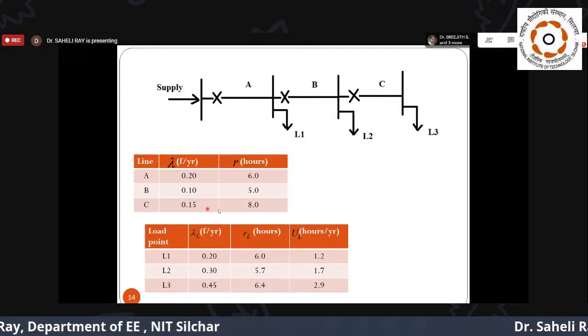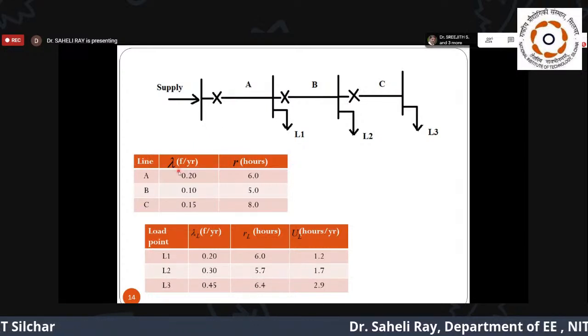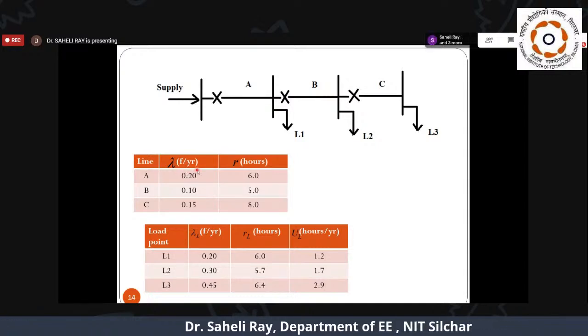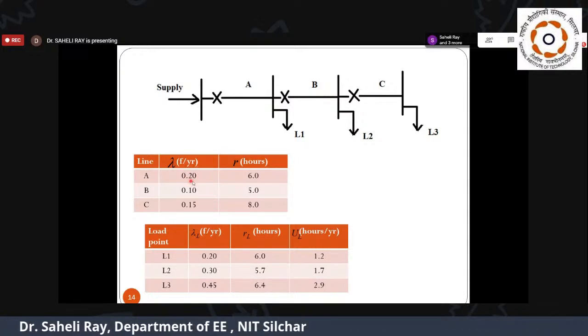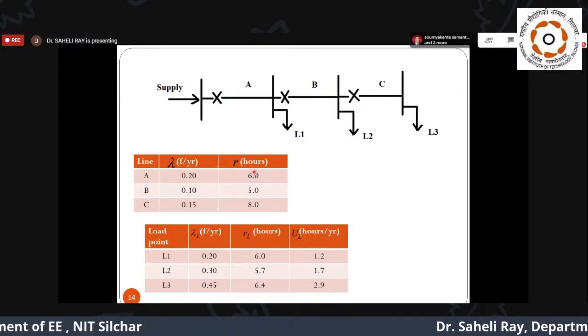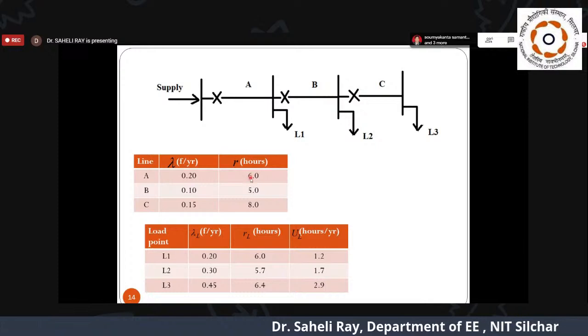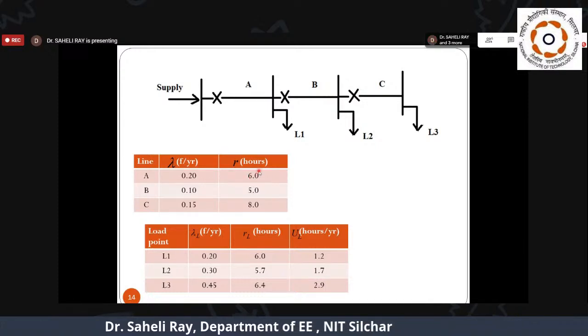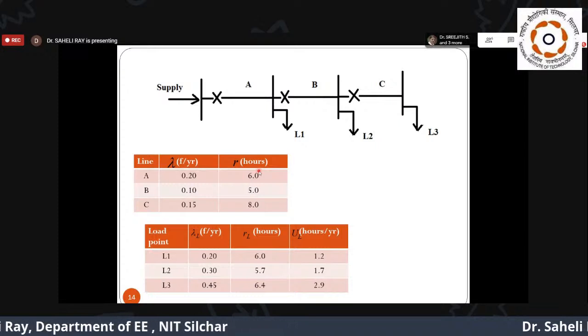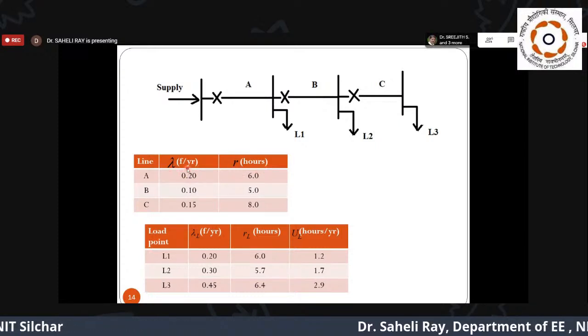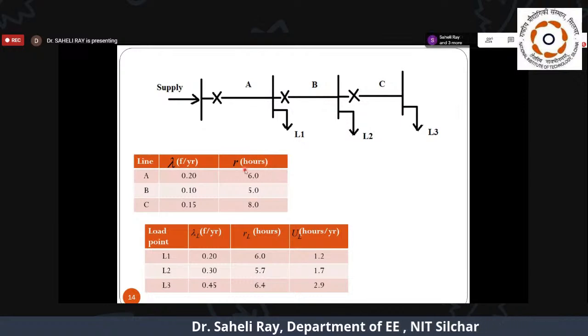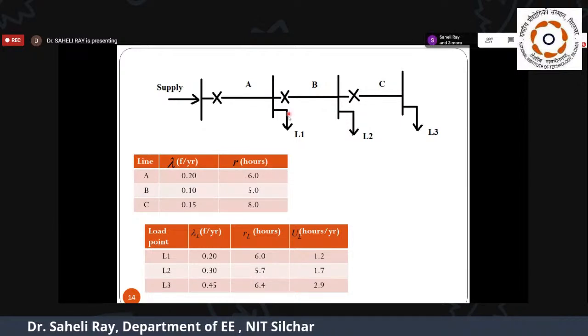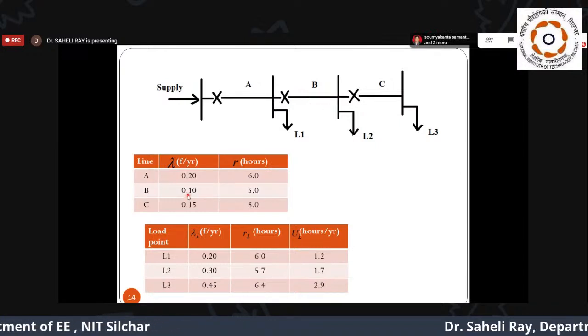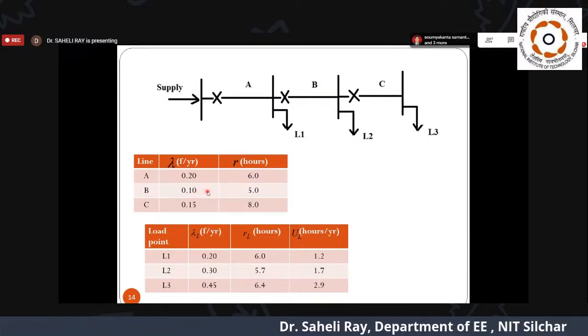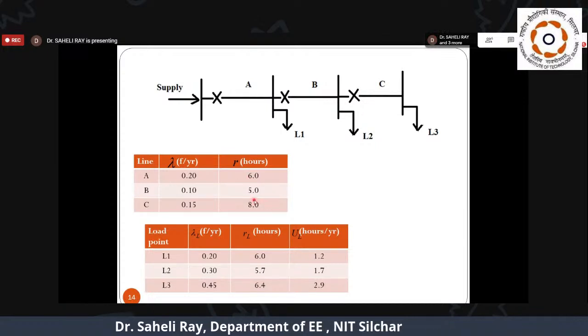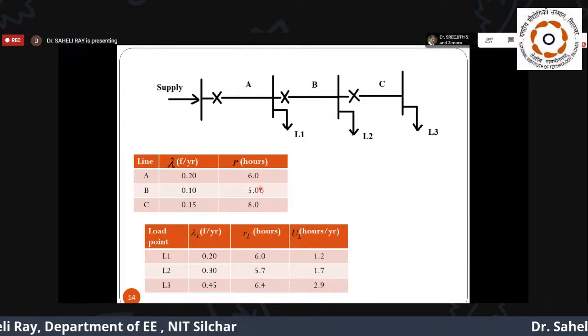We are given this first table of data. For line A, the failure rate is 0.2 per year, and once a failure occurs, the average time to repair it is 6.0 hours. Similarly, for section B, the failure rate is 0.1 per year, and 5 hours is required to repair that failure once it occurs.